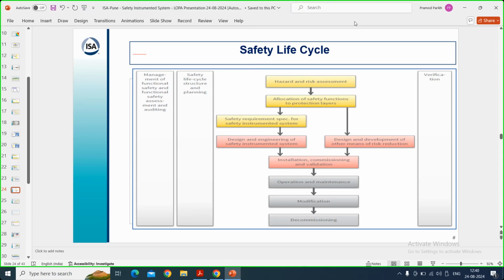Probably how many people have done SIL verification? Have you verified your SIL? What I want to say is you have to verify the SIL before commissioning. You have to first validate it against the SRS. Do you have documentation of how you selected the SIL? If it is properly documented, then you can verify. But verification again needs the frequency of testing to be decided. As I mentioned, a SIS is a dormant system. Unless you test it, you will not come to know.